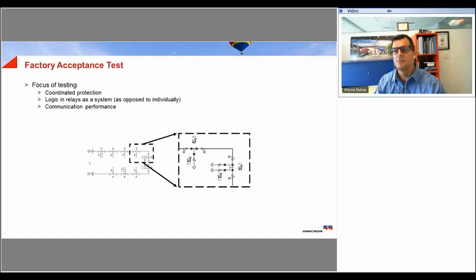So even though this scheme utilized fairly simple protection elements, there's a lot of added complexity when it came to testing because of the communication assisted logic. So this logic required much more attention to detail in testing, which is often difficult to perform via the traditional methods which we mentioned. So in order to test the logic using traditional methods, a tester would have to be able to simulate the adjacent relays in order to mimic their communication just to satisfy the internal logic states.